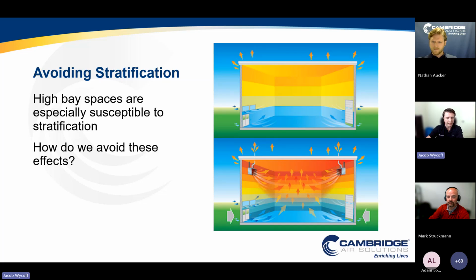That's going to result in the people down in the occupied space being cold, the thermostats reading a cold temperature, which is going to keep the equipment running for a long time. And you're going to have a very hot roof line, that's going to basically increase the temperature difference between the inside of your roof and the outside of your roof, which is going to make you lose even more heat out of your roof than necessary. So we know that this is a huge issue in these high bay spaces if you are experiencing stratification. So how do we avoid that?